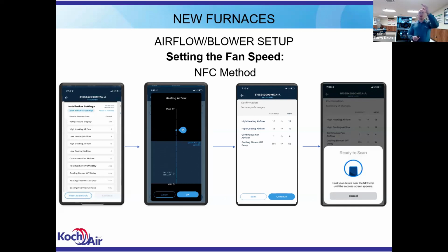But you can see on that particular example, you can set it from the speed 3 up to speed 17. It's not going to give you the full 25. It's going to limit because of that furnace model. That furnace model and serial number is coded into the board. So it knows exactly what furnace it's in, the width of the furnace, the blower, the drive size, the BTU size, knows all that. It's only going to allow you to set the fan speed to within the parameters that are associated with that exact furnace model.